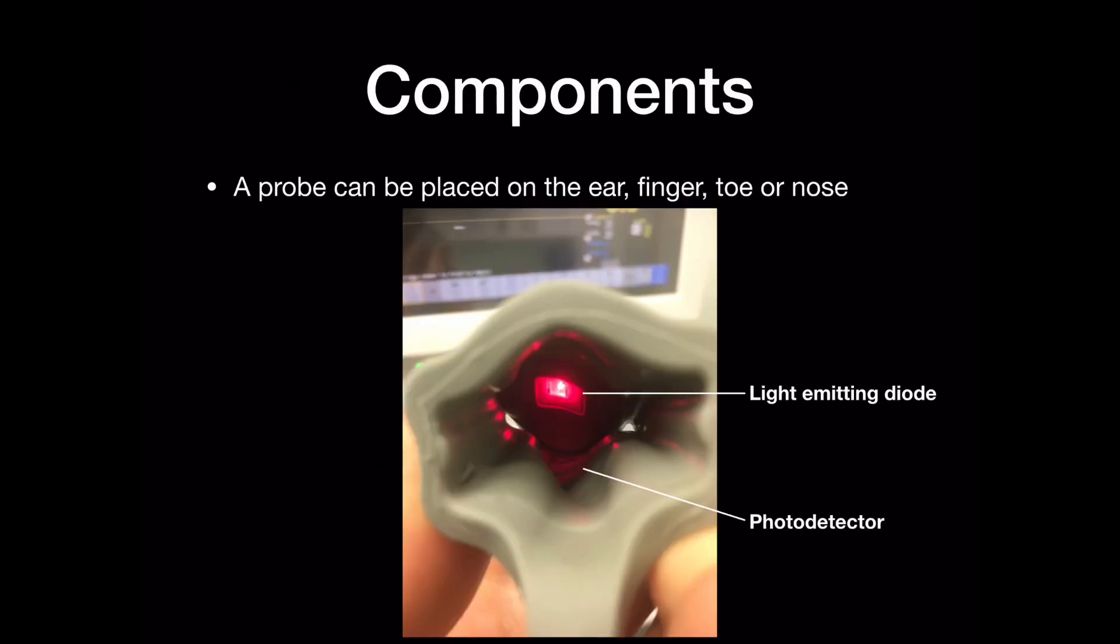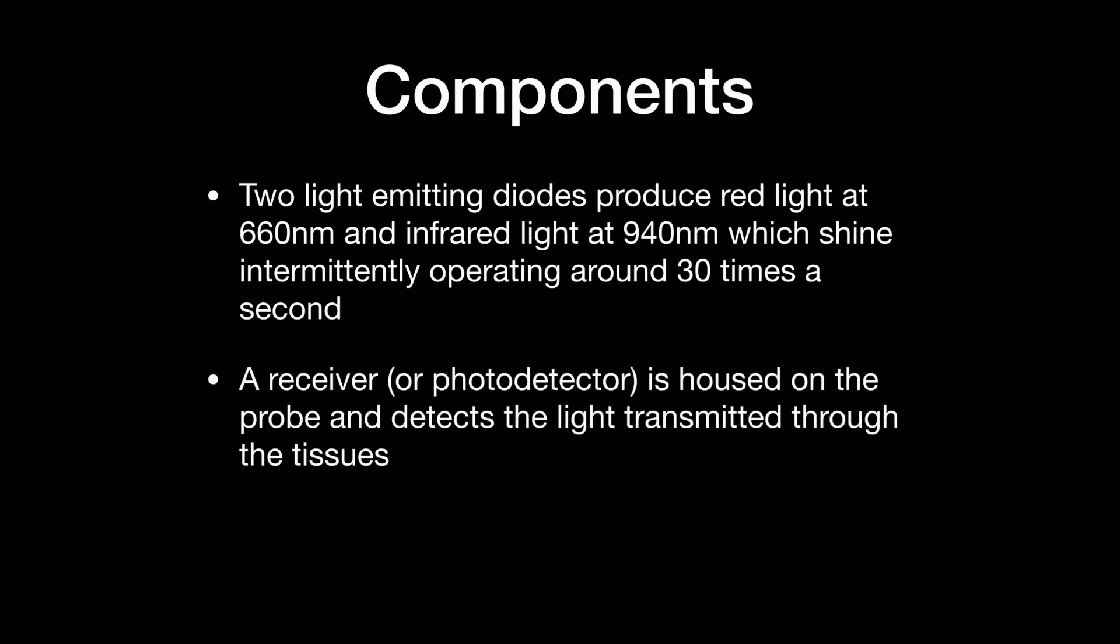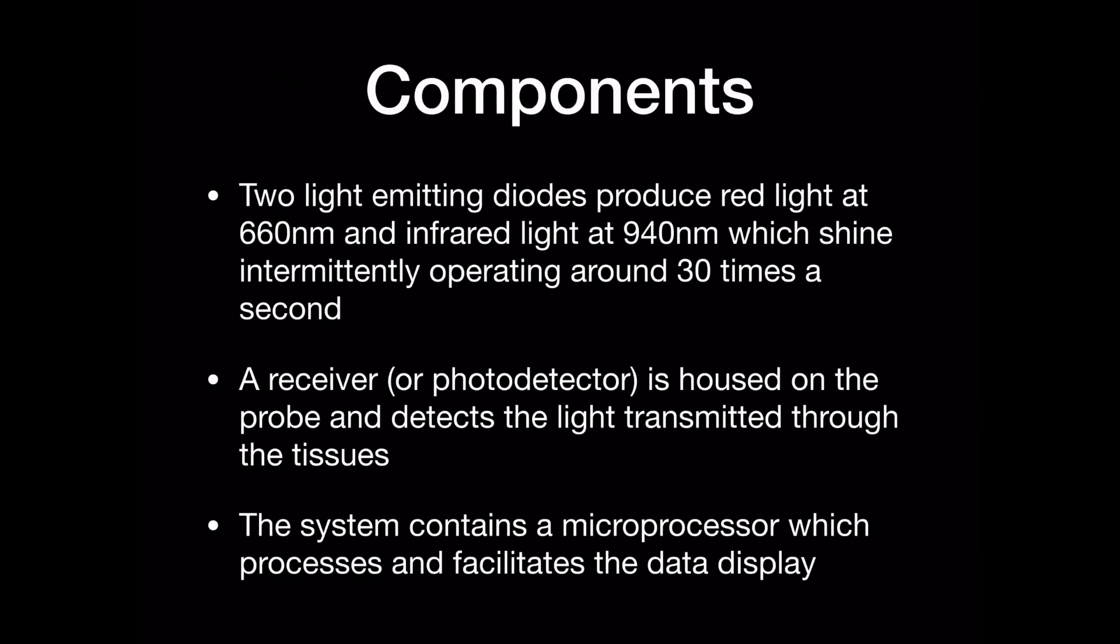Components. A probe can be placed on the ear, finger, toe or nose and two light emitting diodes produce red light at 660 nanometers and infrared light at 940 nanometers. These two light wavelengths shine intermittently operating around 30 times a second. A receiver housed on the probe detects the light transmitted through the tissues and the system contains a microprocessor which processes and facilitates the data.